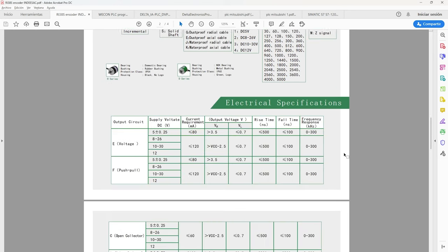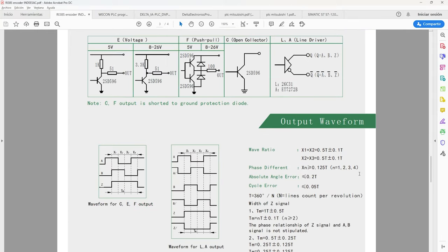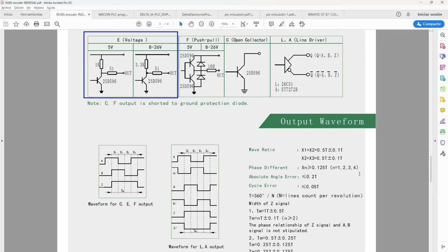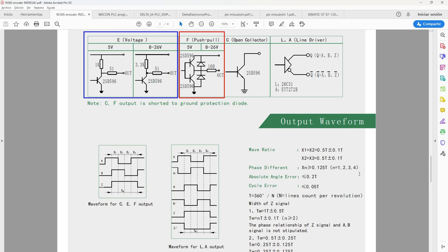Now we are going to briefly specify the output circuit of an encoder. Type E refers to the voltage of the resistor connected to the transistor. Type F is composed of two transistors and two diodes which allows it to operate in NPN and PNP signals. This circuit is called push-pull. Type C refers to the voltage of the transistor called open collector.